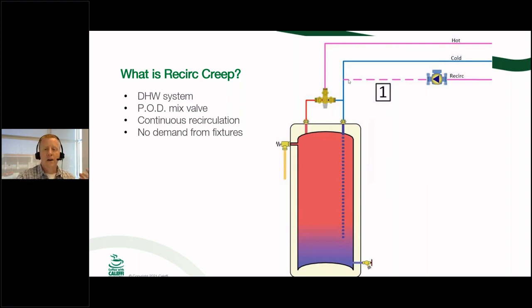So again, you've got your recirc coming back 110, 115. Most of it's going into this cold inlet, but some of it's going to go back through this tank, and it's going to come back to this hot inlet. And the issue lies in the fact that in certain scenarios, the mixing valve is not going to be able to close down completely, and actually just not enough is what it boils down to. So what you have the ability to do in that scenario is, if this hot inlet's open a little bit more than it needs to, you're going to have the ability to add more heat to the loop than what the loop is giving off.